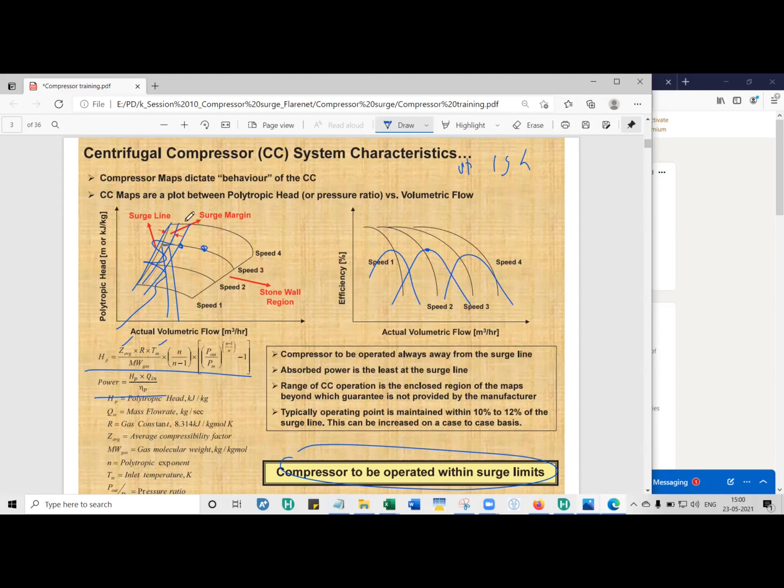When a manufacturer provides you with the performance curves, the polytropic head versus the actual volumetric flow rate, the operating point must operate as close as possible to the maximum efficiency. At lower efficiencies, again, you require more power to compress the gas. So, and on a final note, always, always operate the gas compressor within the allowable limits to prevent mechanical damage.